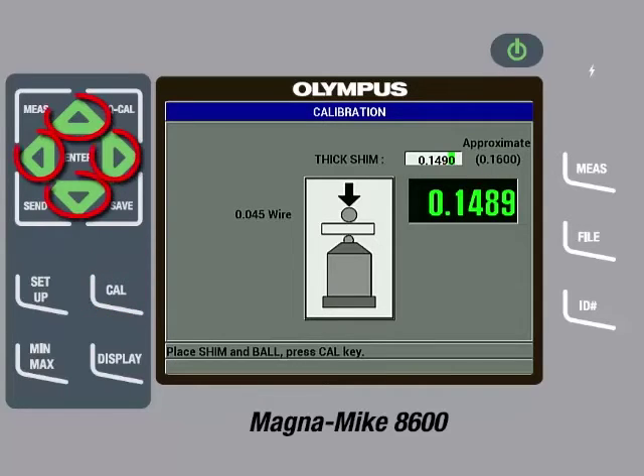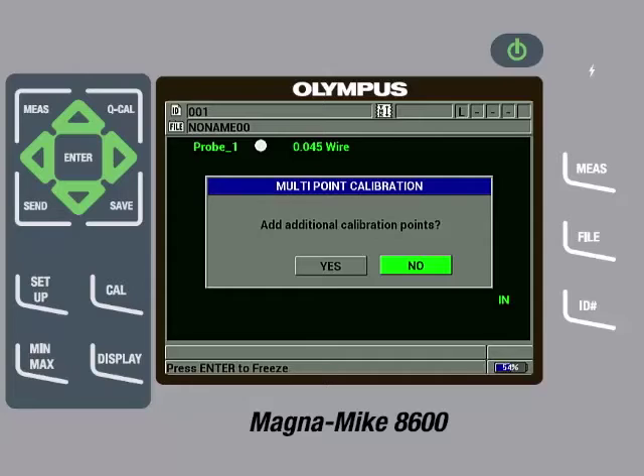Then use the arrow keys to input the precise thickness of the shim, which in this case is 0.1600 inches or 4.064 millimeters. Then press the cal key. The gauge will then ask if we want to add additional calibration points. If we choose no, the calibration process is over and we have completed a basic calibration. The recommendation is to always add additional calibration points since it improves measurement accuracy.